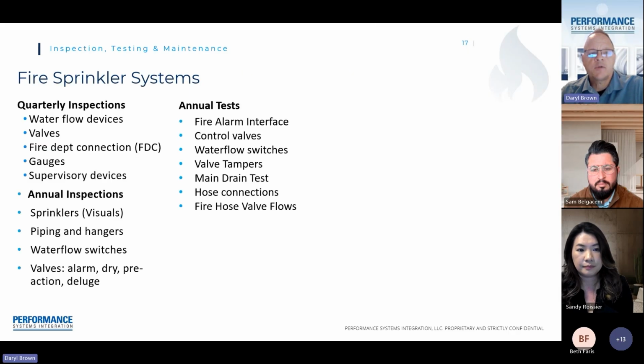So to summarize the inspections and tests we have for fire sprinkler systems, we have quarterly items and annual items, whether it be for inspections or testing items that are done on an annual basis. And this gives you a breakdown of generally what's done during quarterlies and annual inspections and tests.